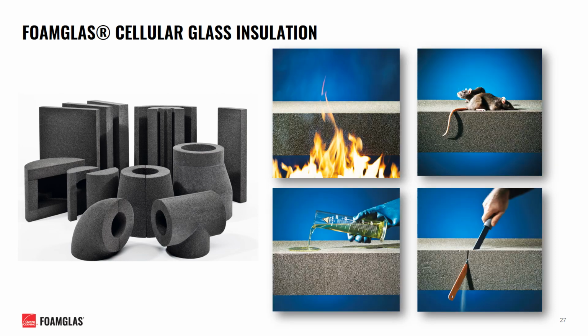Being 100% inorganic and made of glass, foam glass is non-combustible and does not give off dangerous gases in the event of a fire, making it suitable for fire protection and fire stop applications. It also is resistant to the nesting activities of common vermin and rodents that may be found in an area, and is chemically resistant in a similar fashion to many typical glass beakers you may expect in a laboratory. Finally, it's easy to cut and can be fabricated in the field or prefabricated to many different shapes and configurations prior to arriving on a job site.